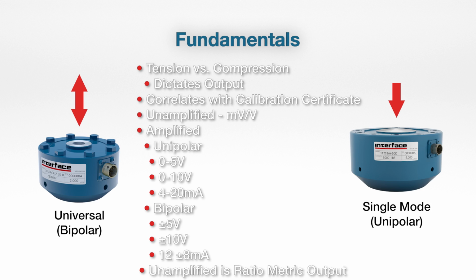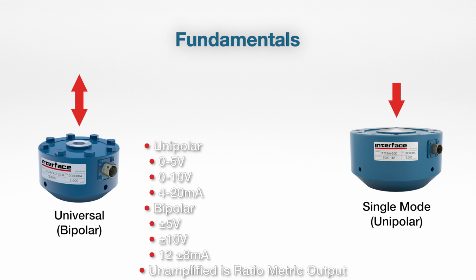Standard output from the vast majority of our load cells is going to be an unamplified millivolt-per-volt ratiometric signal. We'll come back and hit that again a little bit here. We do have amplified signals available as well. Oftentimes customers will require that to interface with their data acquisition units. Some examples of amplified unipolar signals would be a 0 to 5 volt output, a 0 to 10 volt, or a 4 to 20 signal. Examples of bipolar amplified outputs would be plus or minus 5 volts, plus or minus 10 volts, and in some instances 12 plus or minus 8 milliamps. Again, the unamplified output is going to be a ratiometric millivolt-per-volt output, and we've got some examples on the next slide.